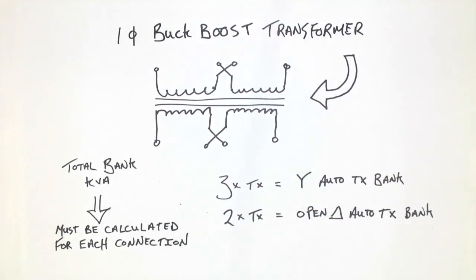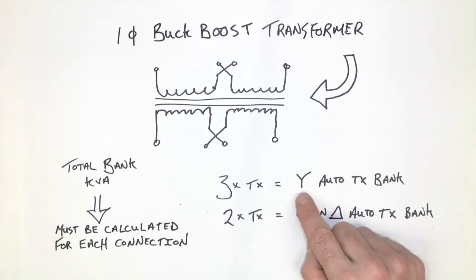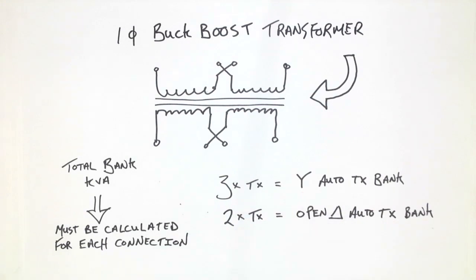Now, if we had 3 of these transformers, we could make a Y auto transformer bank for 3-phase. If we had 2 of these transformers, we could make an open delta 3-phase auto transformer bank. When we're connecting isolation type transformers into auto configuration, we will find that the kVA that they are able to provide to a load is increased significantly. And so because of that, the total bank kVA must be calculated for each connection.